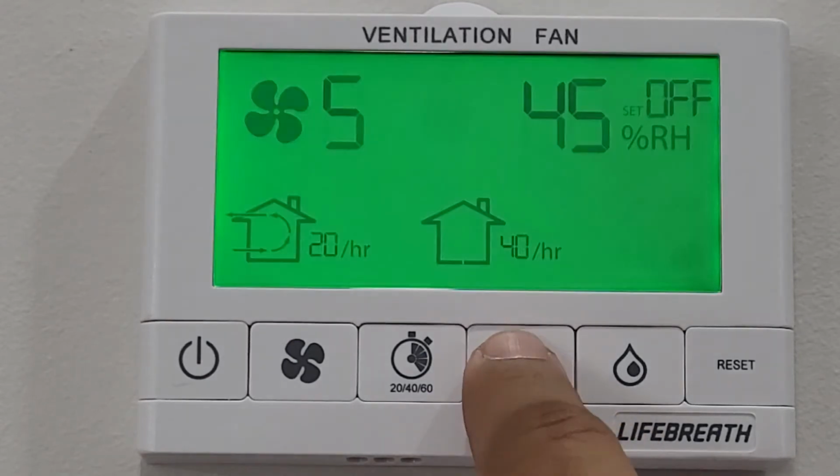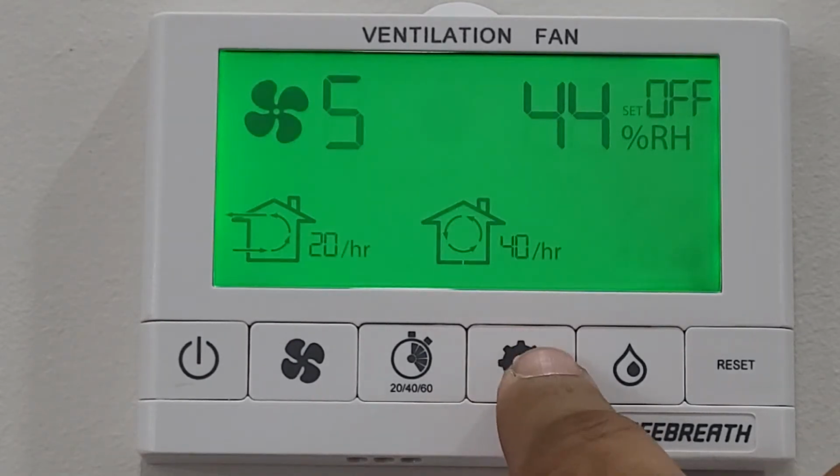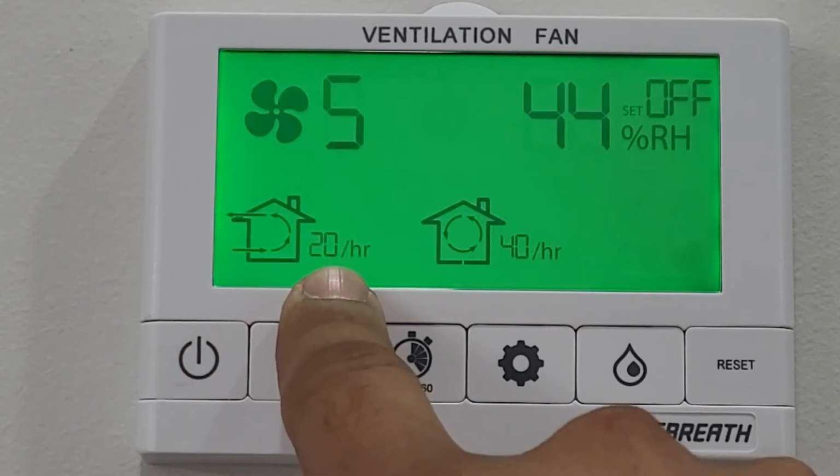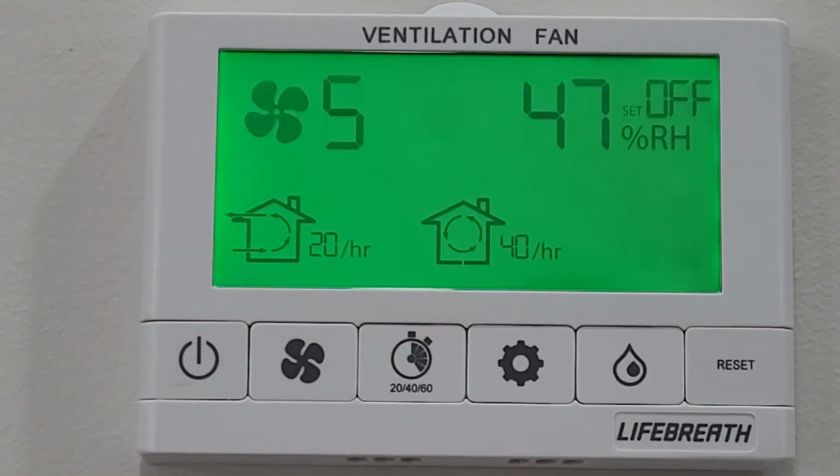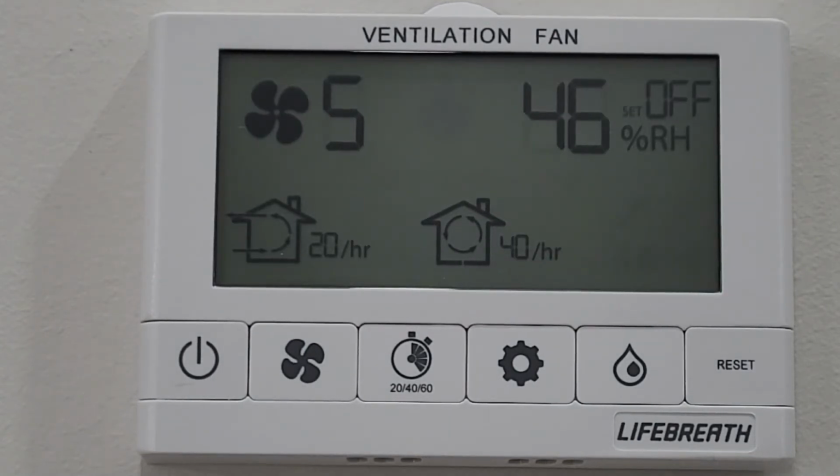And then the second option that I highly recommend is going 20 minutes on and 40 minutes recirculation. Yes, I understand in this one your HRV will be running all the time, but the system will be ventilating for 20 minutes, and then for 40 minutes there will be a continuous airflow, as sometimes with AC you feel humid or damp in your house. So this will solve that problem because your air is continuously moving.